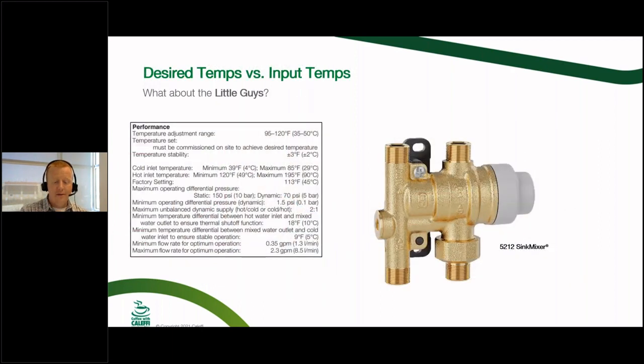Now we also have some requirements for some of the little guys here too, the under sink mixing valves, our sink mixer here. This one is going to have that temperature difference from hot inlet to mixed outlet as well. But what we also note in here is a minimum temperature difference between hot water inlet and mixed water outlet to ensure thermal shutoff function. Okay, 18 degrees here. And what does that really mean?